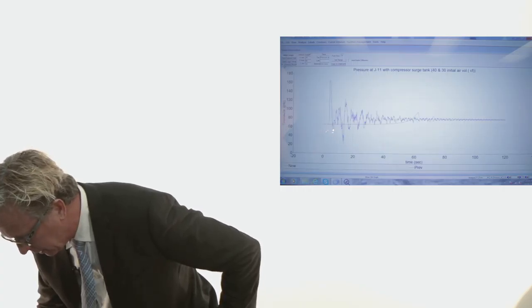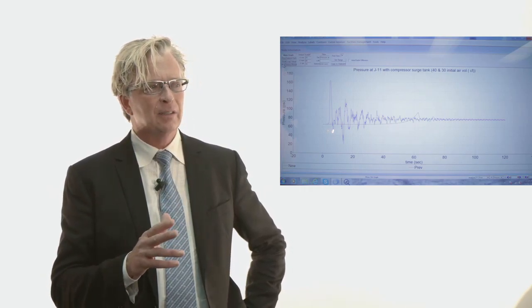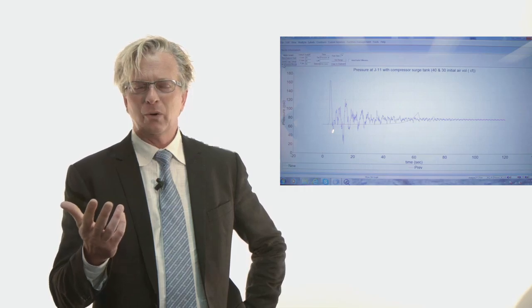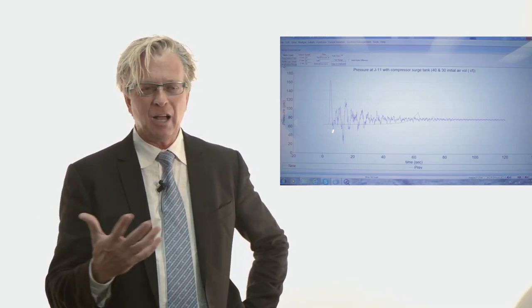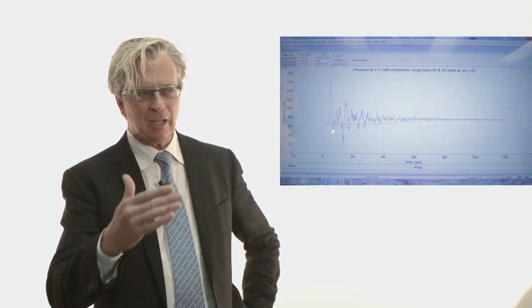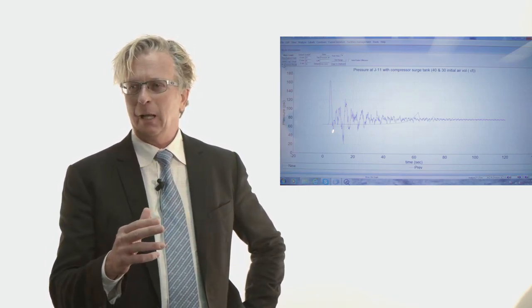Here's the pressure difference between that customer closing in 2 seconds versus 60 seconds. As you're supplying reuse water, you might not be in control of the customer's selection of valve — but by evaluating your whole system and having your plans and specs call out that the valve will close in 60 seconds, you have a well-maintained system. You can see how modeling helps to evaluate and understand your system, look at the worst case scenario — be it your air valves in the field, how your control valves are set, or the design of the reuse pump station itself — including the need for a surge vessel to give and receive energy for starting and stopping of pumps and pump control valves.